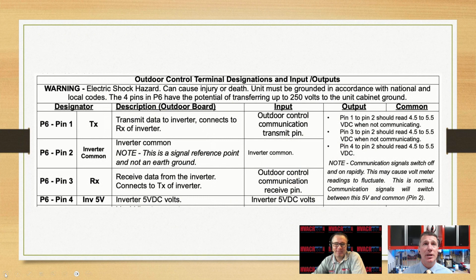What we're there to do is to make sure we have a good network. Remember, it's about the network parameters. It's within parameters. If it's out of parameters, well, we're service technicians. We've got to go find why it's out of parameters, and usually it's going to be a bad conductor of some nature.